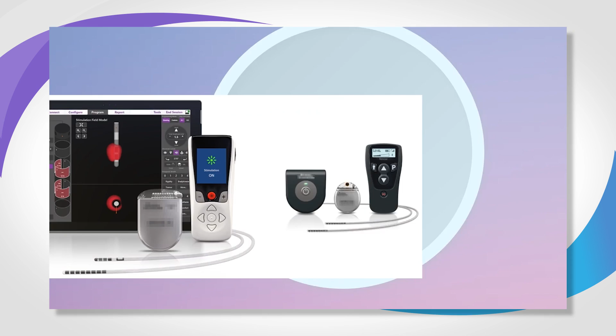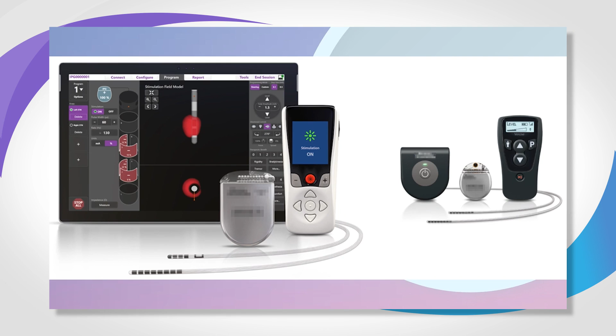The next device is the Boston Scientific device. Here's the clinician programmer. On the bottom, you see the 8 contact linear lead. Above that is the segmented lead with 8 contacts, the Boston Scientific battery, and the patient programmer. What I forgot to mention before is that the Medtronic device and the Boston Scientific device are both MRI conditional, so we can have patients have full body MRI imaging under certain conditions. This Boston Scientific device is rechargeable, and on the right here is the charging unit.